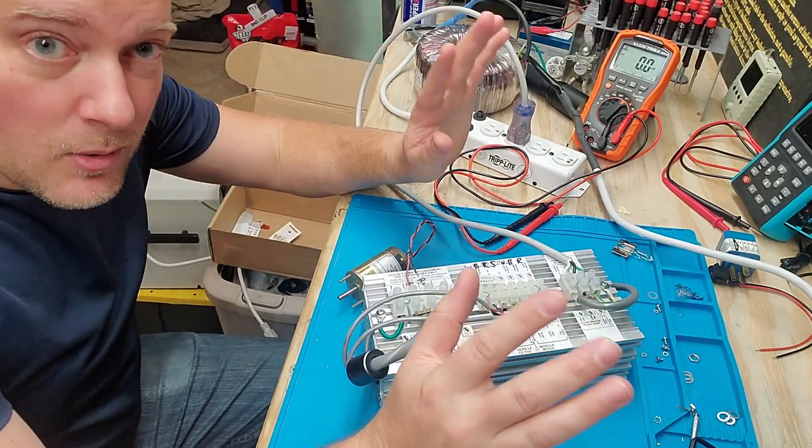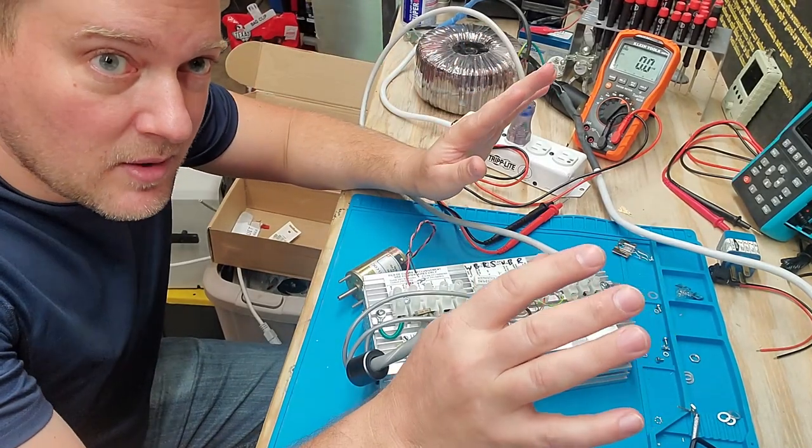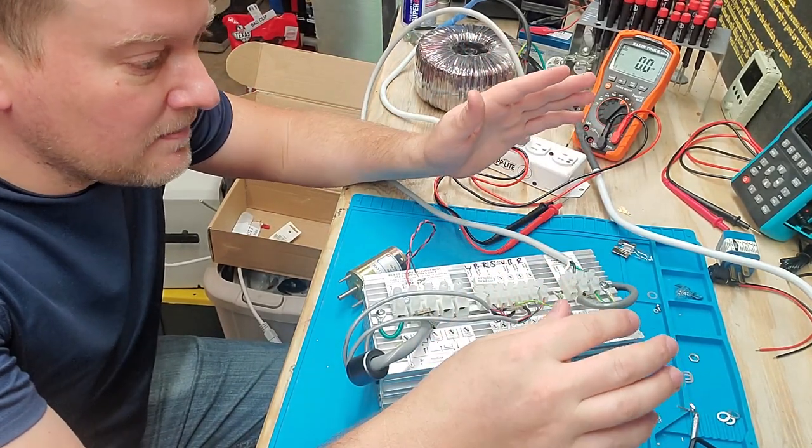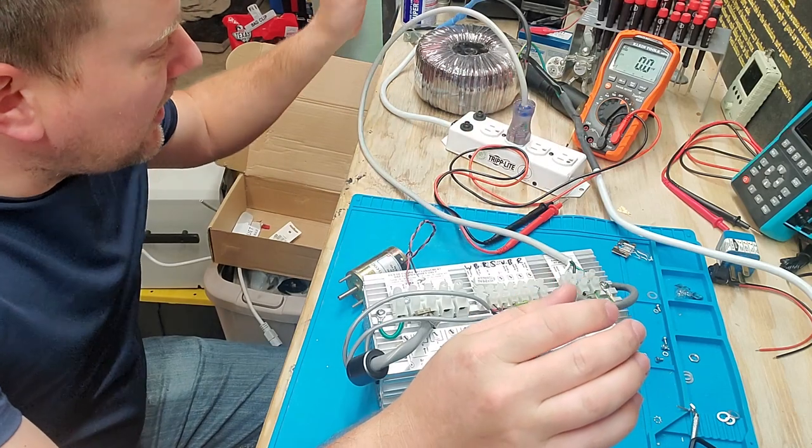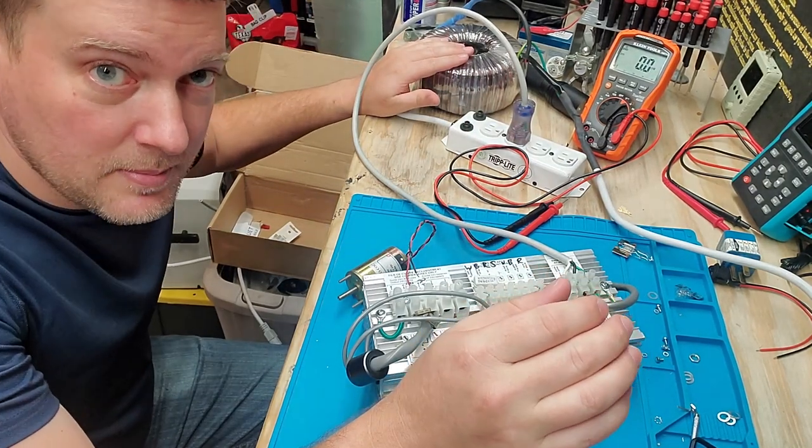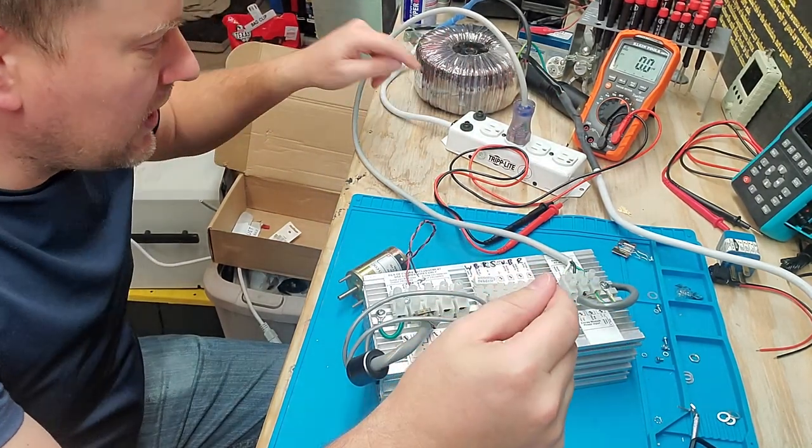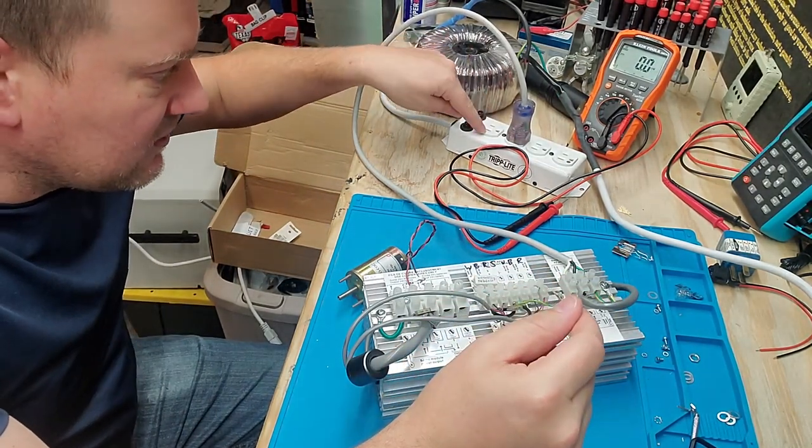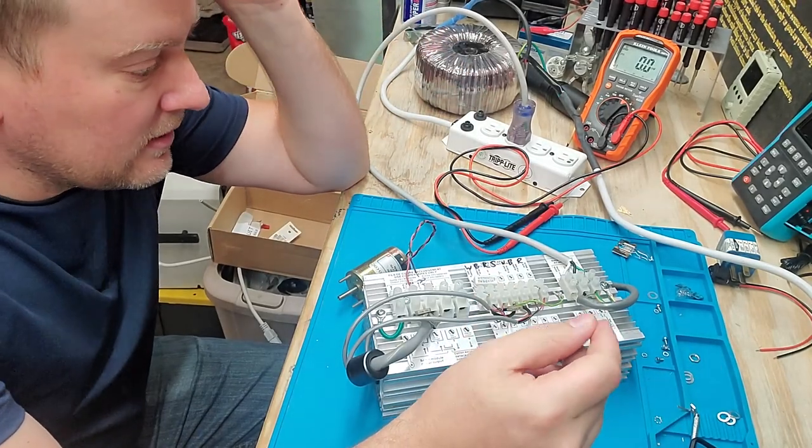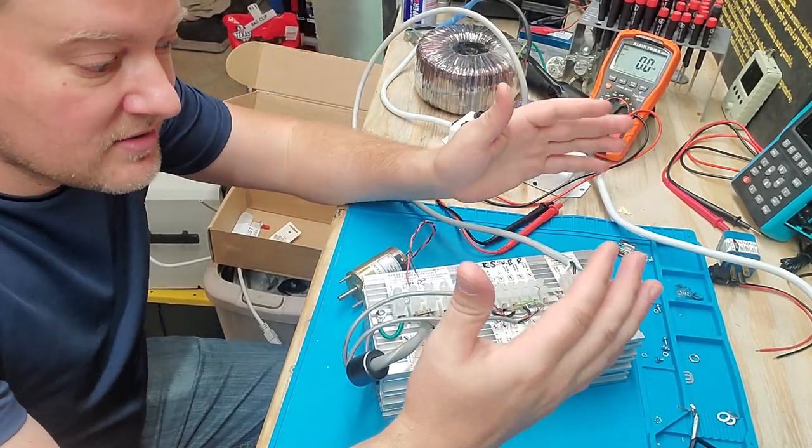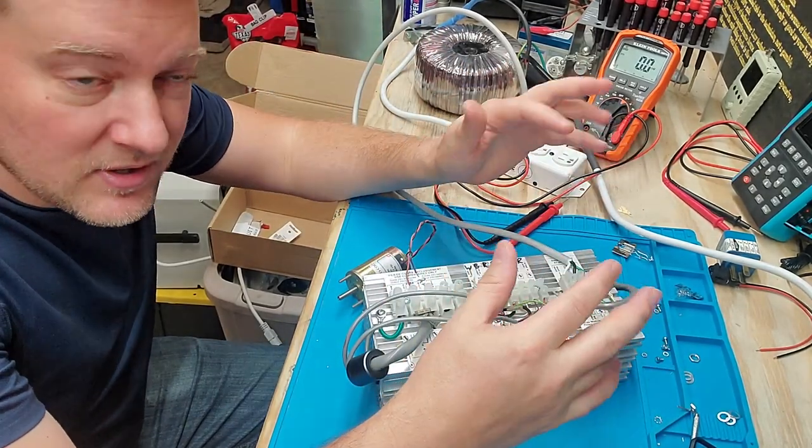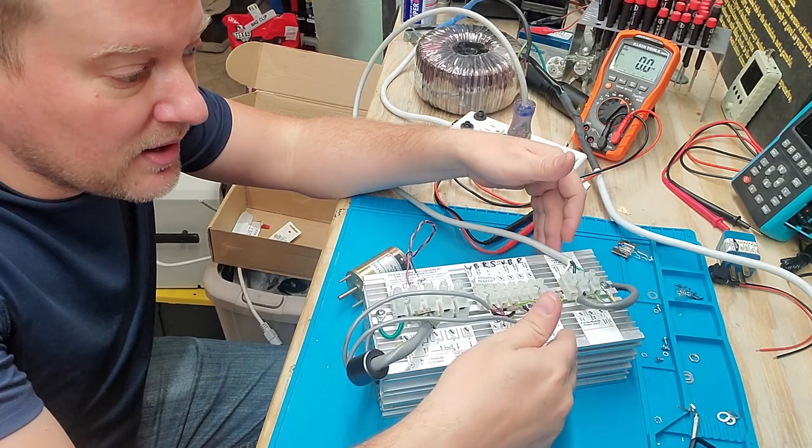So in order to set this up here safely in my environment so I can test it, I have an isolation transformer set up here, so I should have 60 volts per leg.